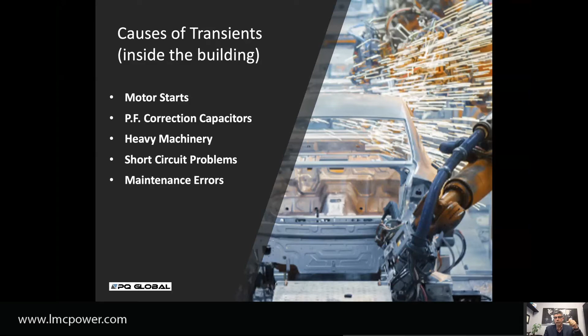Here's a little drawing of a capacitor switching inside a building. A lot of people have power factor correction capacitors in the building, and anytime that capacitor switches from one to another or corrects, it generates a transient. So equipment designed to solve one problem ends up creating other problems.